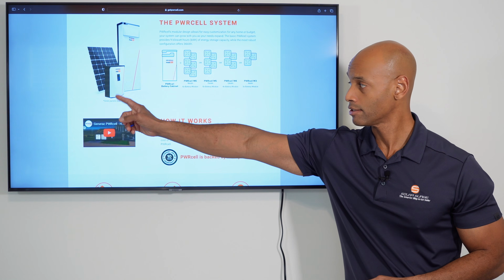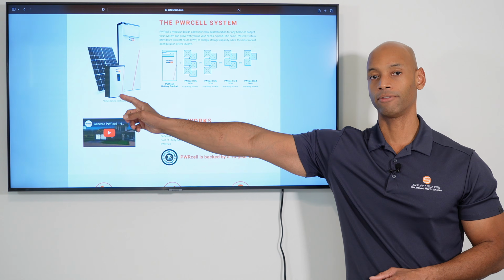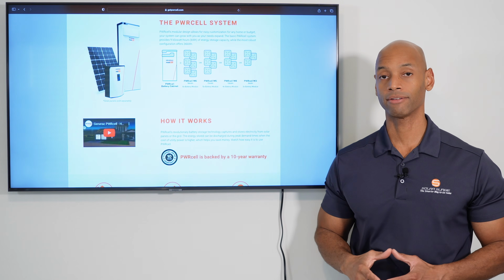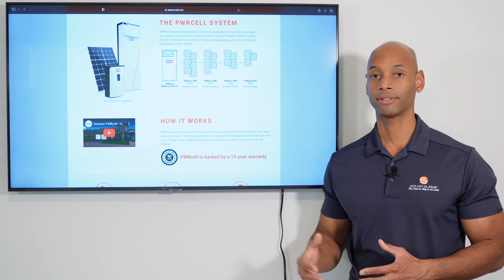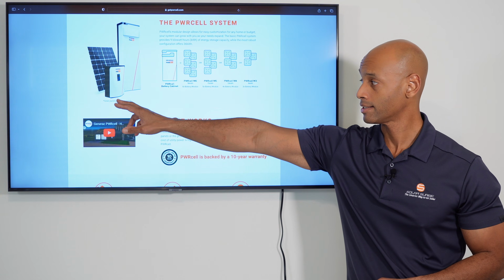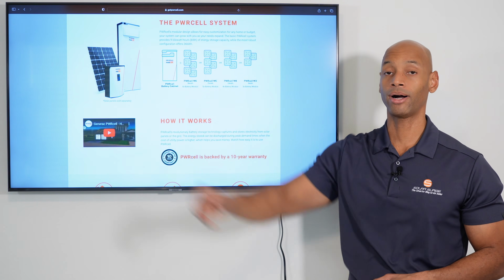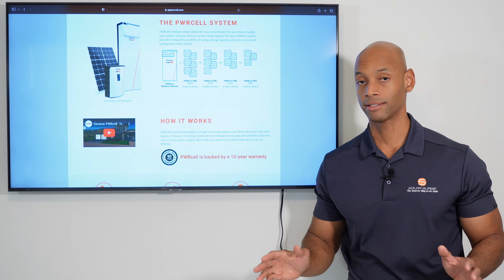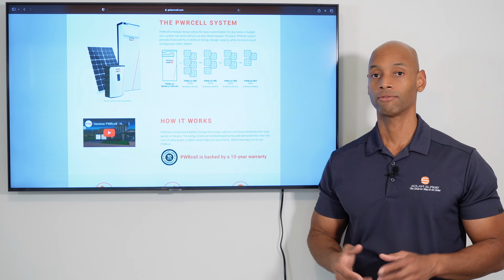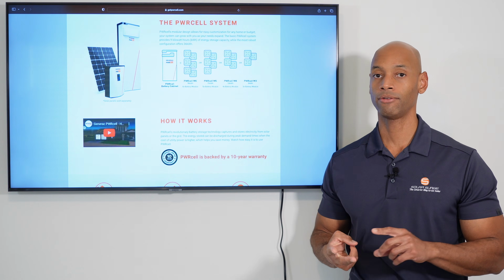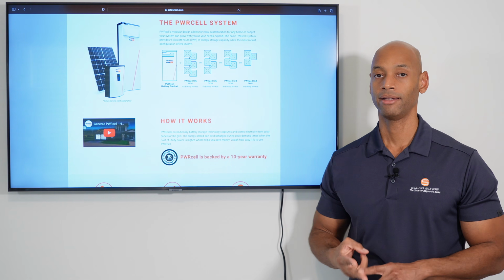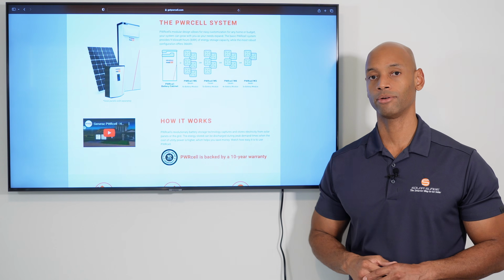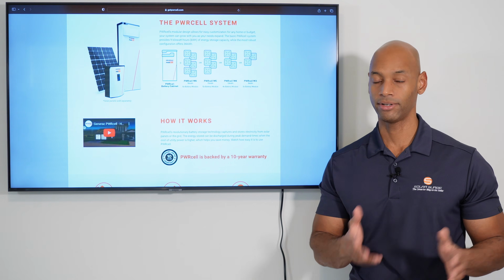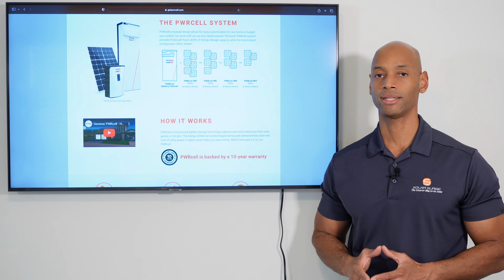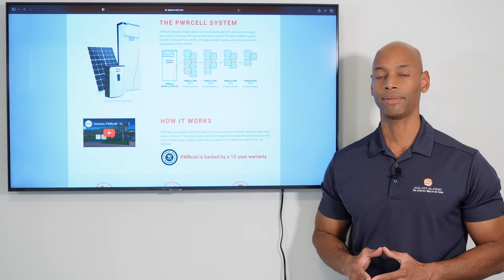If everything has to flow through the inverter, the inverter acts not only as a central point of failure but also as a bottleneck. So if you have an inverter rated for 7,600 watts, that's all you're going to get out of the system, regardless of how much solar is on the roof or how much energy is in the battery. If 7,600 watts is the continuous load rating, that's what you can use in the house when running on backup power.